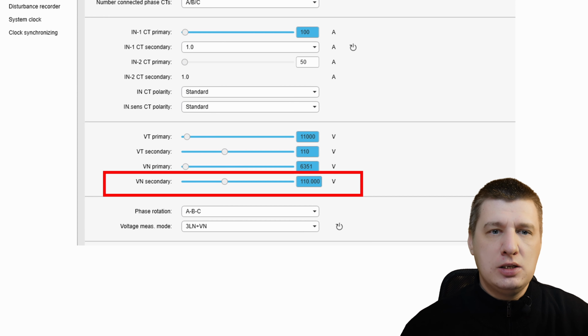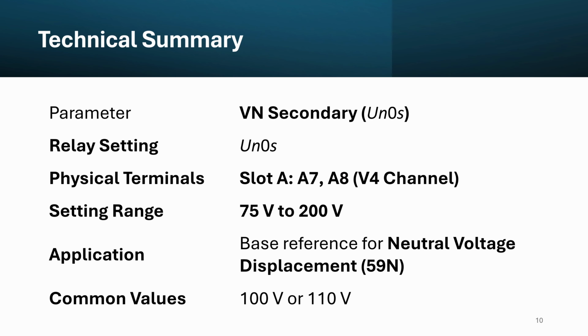The P5 is designed to be compatible with almost any system or standard with the VT. Imagine VN secondary is like the full mark on a measuring jug. The jug, your VT, might hold 11000 liters of water in the real world, but in the relay's world, that same amount is represented by 110. You have to tell the relay that when the water hits the 110 line, it means the system is full or reaching its rated limit. If you don't define where the full line is, the relay won't know how to spot a fault.